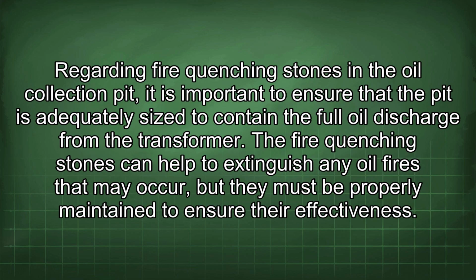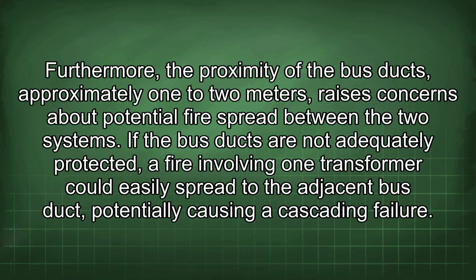Regarding fire-quenching stones in the oil collection pit, it is important to ensure that the pit is adequately sized to contain the full oil discharge from the transformer. The fire-quenching stones can help to extinguish any oil fires that may occur, but they must be properly maintained to ensure their effectiveness. Furthermore, the proximity of the bus ducts, approximately 1 to 2 meters, raises concerns about potential fire spread between the two systems.